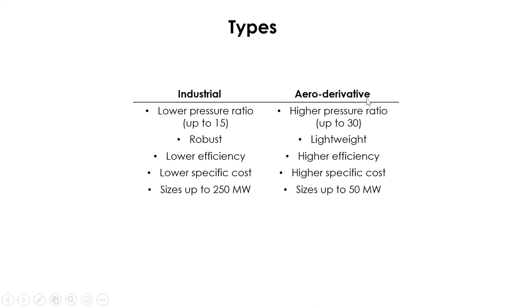On the other hand, the aero derivative machine can operate at a high pressure ratio up to 30, is lighter, more efficient, more expensive, and smaller in size up to 50 MW. Aero derivative gas turbines are typically used for offshore applications where weight and efficiency are premium, to drive compressors for natural gas pipelines, and for standalone power generation for peak periods of high power demand.